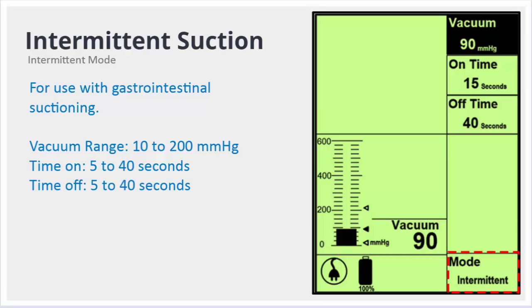The intermittent suction procedure is used for gastrointestinal suctioning with a vacuum range of 10 to 200 millimeters of mercury. Time on and time off are both adjustable from 5 to 40 seconds.